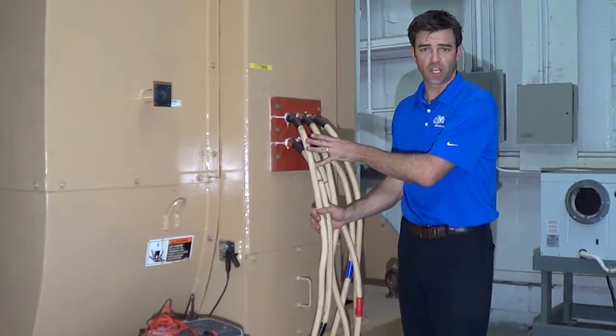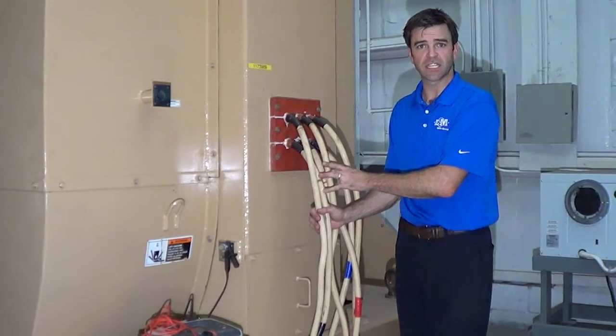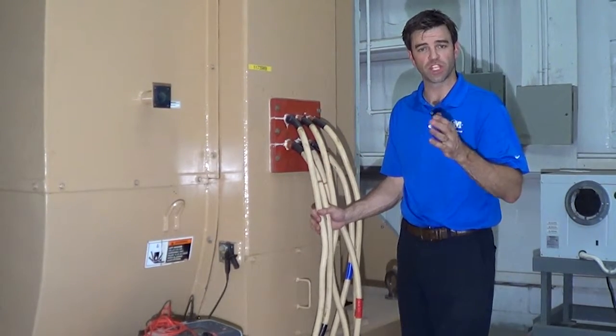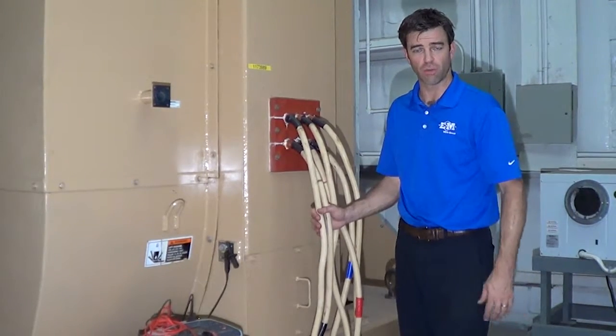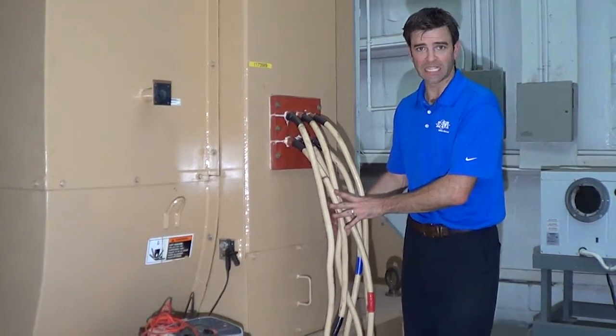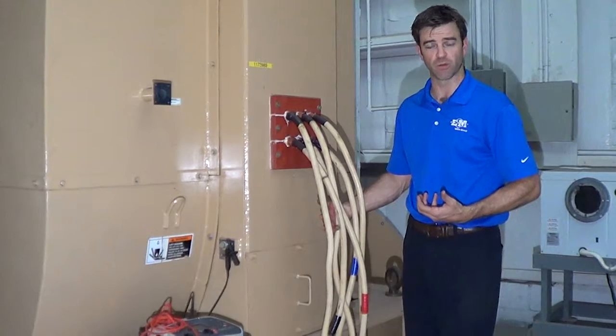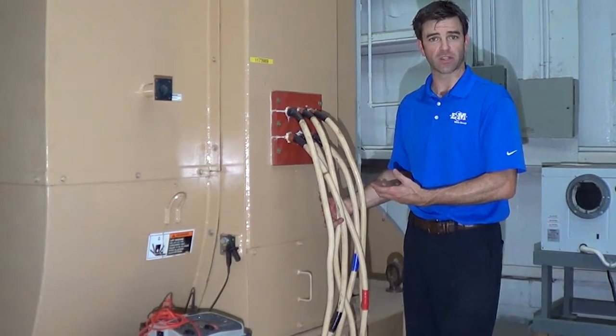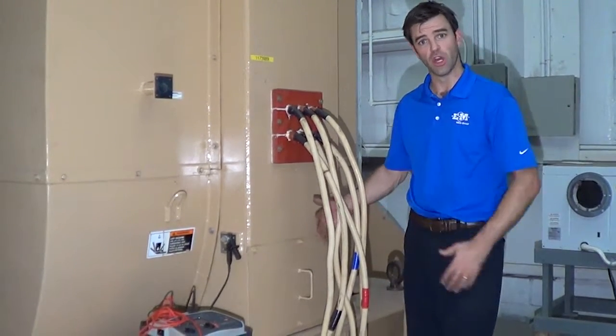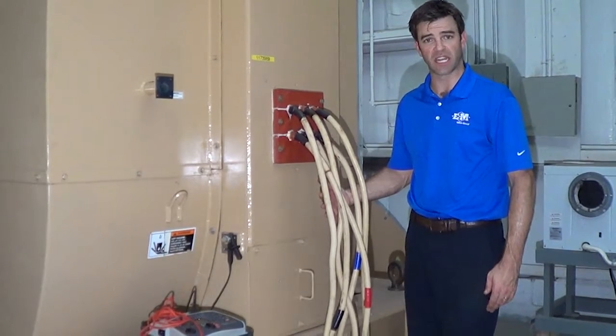This is a 6-lead synchronous motor. 3 of the leads connect to the line going back to the switchgear, and 3 of the leads connect to the neutral bar. You can see all 6 leads have been lifted as the terminal box is removed. Typically, you'll complete electrical testing with the terminal box installed, but all 6 leads need to be disconnected for an accurate test.